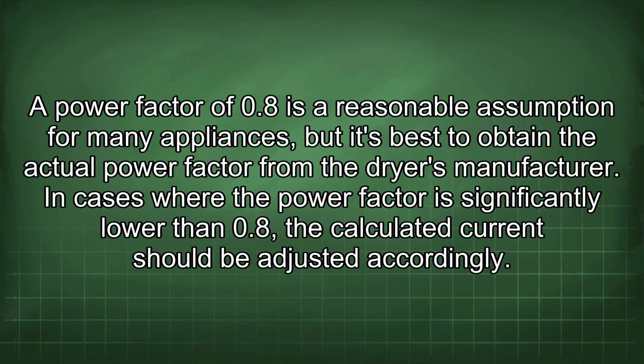A power factor of 0.8 is a reasonable assumption for many appliances, but it's best to obtain the actual power factor from the dryer's manufacturer. In cases where the power factor is significantly lower than 0.8, a calculated current should be adjusted accordingly.